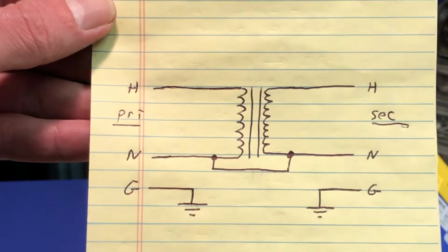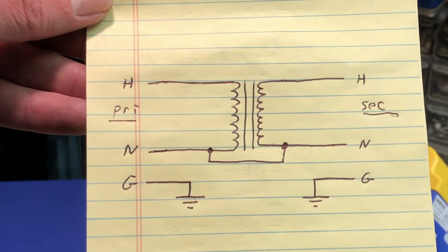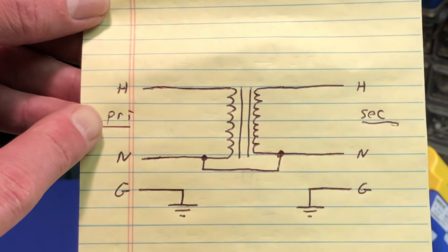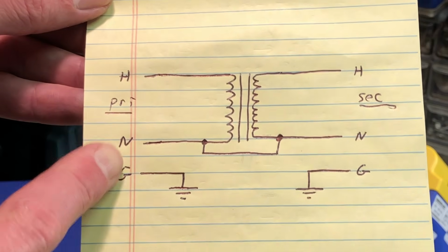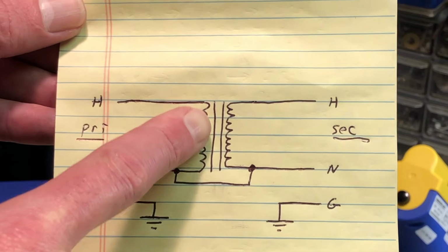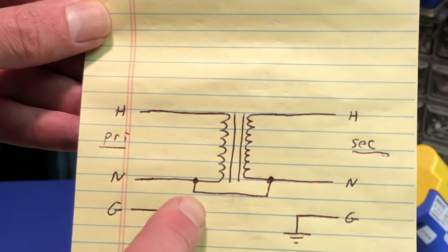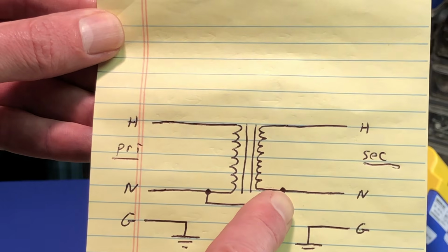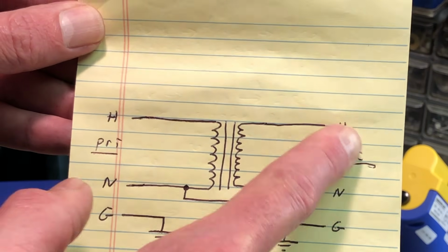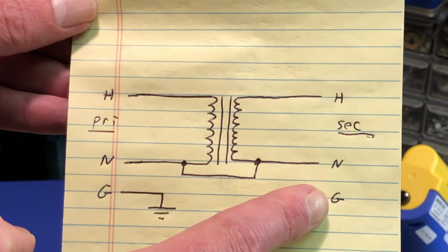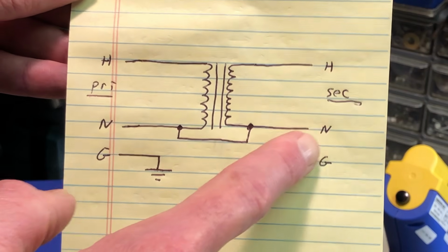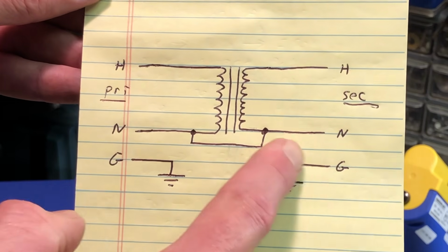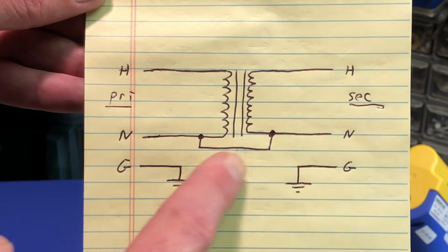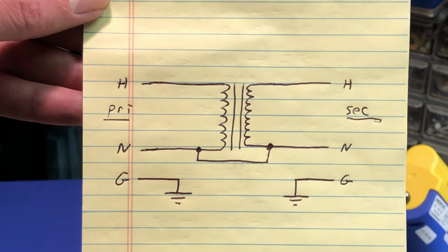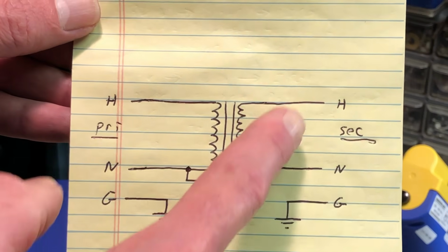So here's a schematic of what is actually inside the unit as the manufacturer assembles them. As you can see over here, we have the primary, we have the hot and the neutral and chassis ground. You can see there's the 1-to-1 isolation transformer. But down here, there's a link on the neutral, all right? So this is the secondary going to the outlets on the back of the unit, so you have the hot, the neutral, and ground. But the neutral here and the neutral over here, so primary to secondary, has a link between them. So this is not an actual isolation transformer.